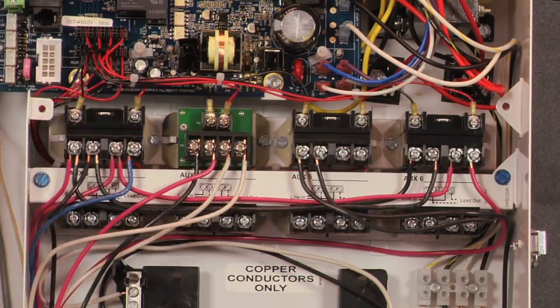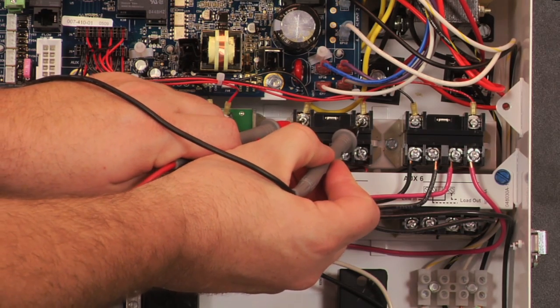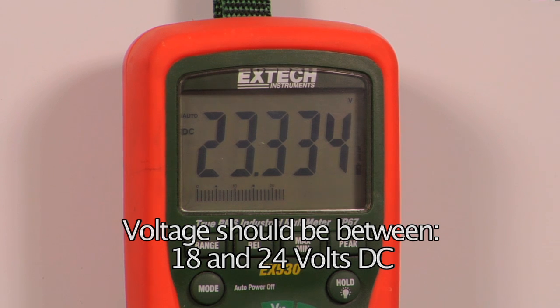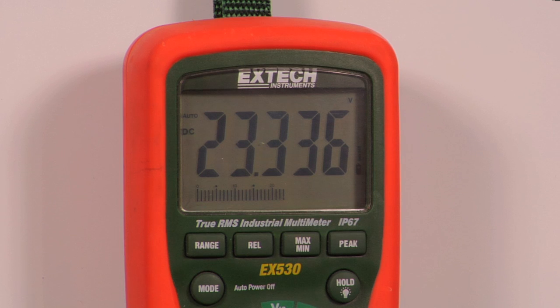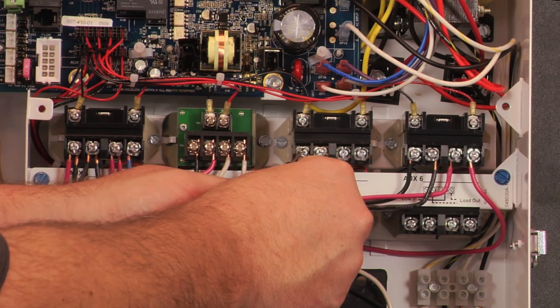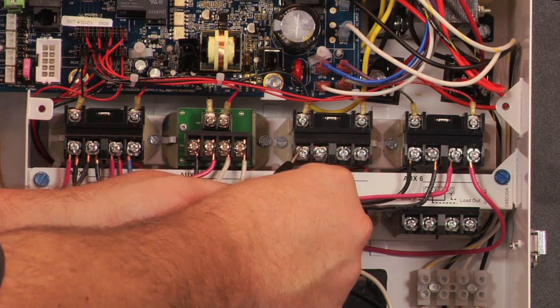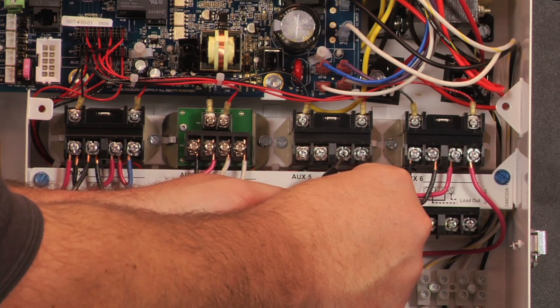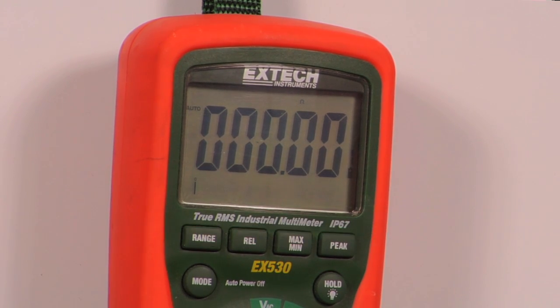Remove the relay cover. Measure the voltage across the relay coil. The reading should be 18 to 24 volts DC. If there is no voltage, replace the main board. If voltage is present, the relay may be bad. With the relay energized, measure the continuity between contact terminals 1 and 2 and 3 and 4. The reading should be 0 ohms. If one or both of the contacts are open, the relay is bad and needs to be replaced. If the contacts are good, then the problem is either in the piece of equipment that is being controlled by the relay or the wiring from the ProLogic to the piece of equipment.